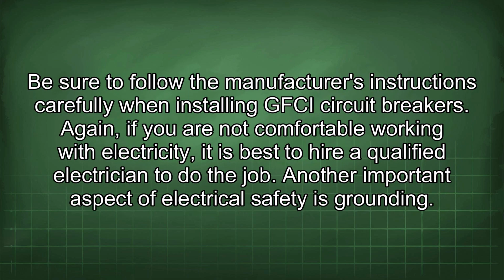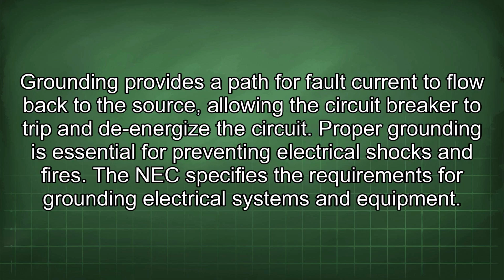Be sure to follow the manufacturer's instructions carefully when installing GFCI circuit breakers. Again, if you are not comfortable working with electricity, it is best to hire a qualified electrician to do the job. Another important aspect of electrical safety is grounding. Grounding provides a path for fault current to flow back to the source, allowing the circuit breaker to trip and de-energize the circuit. Proper grounding is essential for preventing electrical shocks and fires.